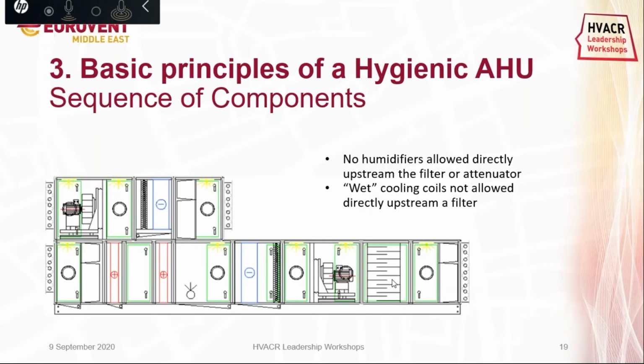But it's not only the materials or selection of the components what affects the hygiene level of a unit, but also the sequence of the components. For example, if you look at these sequence of the components, while selecting the unit, make sure you do not position the humidifier directly upstream a filter or a sound attenuator in order not to make them wet. Also, a wet cooling coil like here should not be positioned directly upstream a filter or sound attenuator.